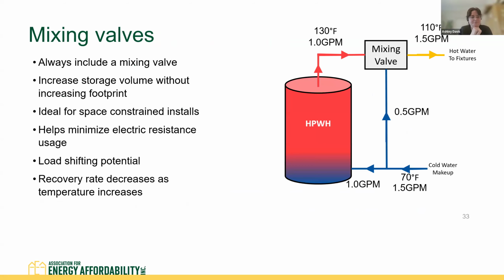Next slide. And then another key design consideration is including a thermostatic mixing valve. This helps increase the storage volume without increasing the footprint. It's good for constrained installs and helps minimize electric resistance usage. And there's potential for load shifting. So basically, the idea with a mixing valve is that you set your heat pump water heater a little higher than your desired delivery temperature. So then you have to pull less water out of your heat pump water heater every time someone draws water at the tap.